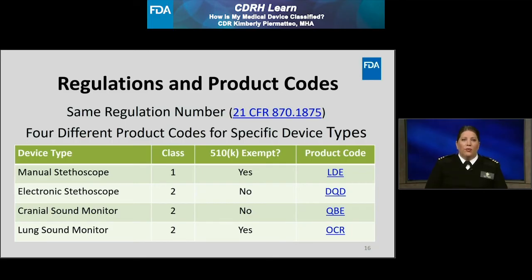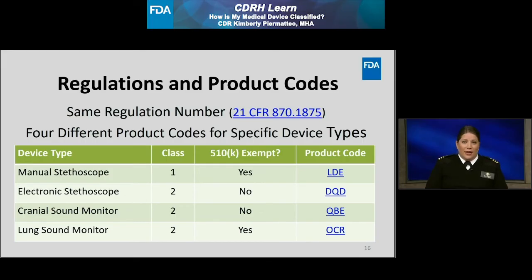For example, regulation number 21 CFR 870.1875 has four different product codes under this one regulation number. A manual stethoscope is considered Class 1 and 510(k) exempt under product code LDE, whereas an electronic stethoscope, which falls under the same regulation number, has a different product code, is considered Class 2, and is not 510(k) exempt. The key point is that when classifying a medical device, it is very important to drill down to the appropriate FDA product code and not just to the class or regulation number.